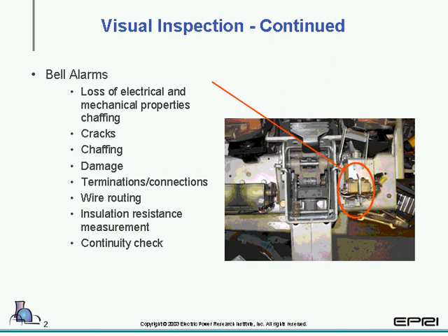Bell alarm. We have a list of items you need to check for the bell alarm. One of the items that should be checked just before you install the breaker, when you're doing your preventative maintenance and you complete your task, is you roll the breaker out in front of the cubicle, getting ready to install it. It is advisable to check the bell alarm one more time to verify that during movement you didn't cause any problems or disturb the actual latching.